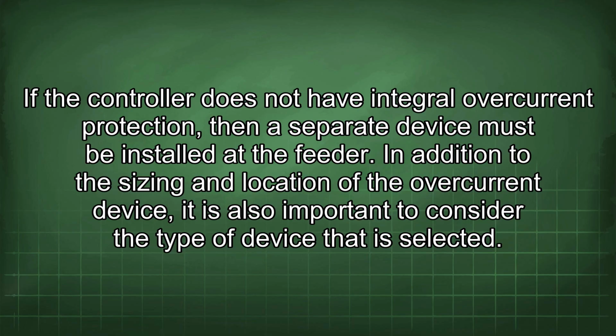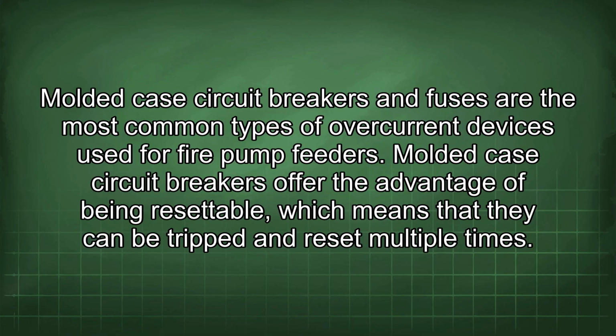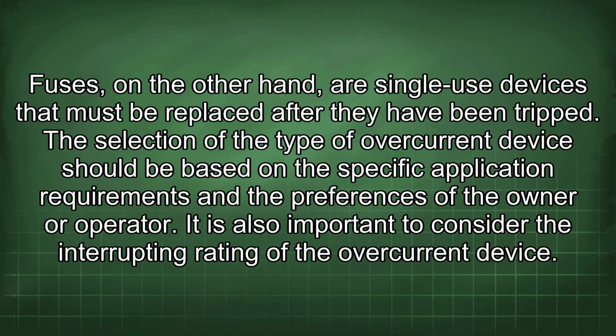In addition to the sizing and location of the overcurrent device, it is also important to consider the type of device that is selected. Molded case circuit breakers and fuses are the most common types of overcurrent devices used for fire pump feeders. Molded case circuit breakers offer the advantage of being resettable, which means that they can be tripped and reset multiple times. Fuses, on the other hand, are single-use devices that must be replaced after they have been tripped. The selection of the type of overcurrent device should be based on the specific application requirements and the preferences of the owner or operator.